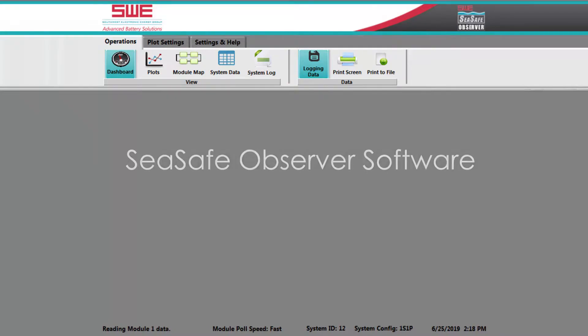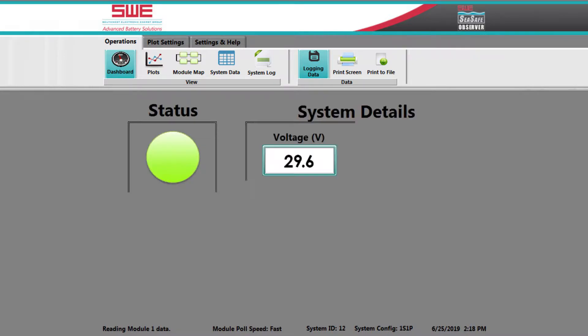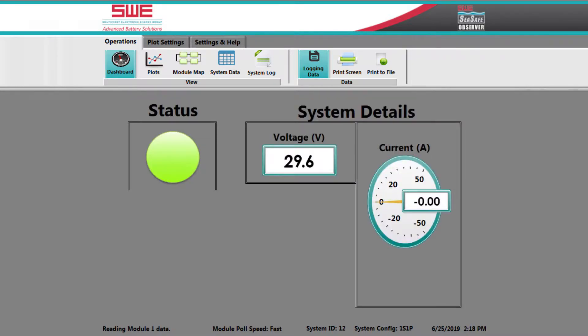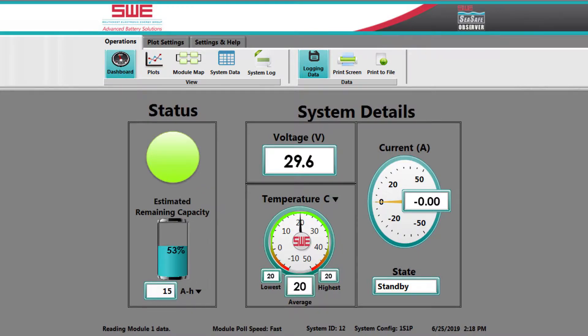I have the SeaSafe Observer software running, which shows the status of the battery, the load volts, and other items. Here you see under status the green light, 29.6 volts, zero current drawing out of the battery on standby mode, with 20 degrees Celsius temperature, and about 53% remaining capacity.